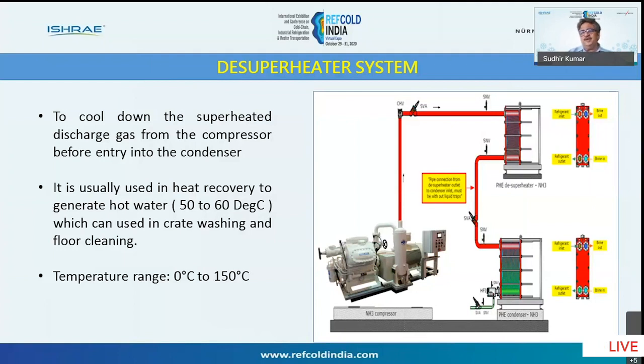Before going into the condenser, we use a heat exchanger. It can be a PHE, a plate type, or a shell and tube. You use it to heat the water to generate hot water. By using this system, your condenser capacity also reduces. At the same time, the COP of the plant increases because you are generating a little amount of hot water in the plant.